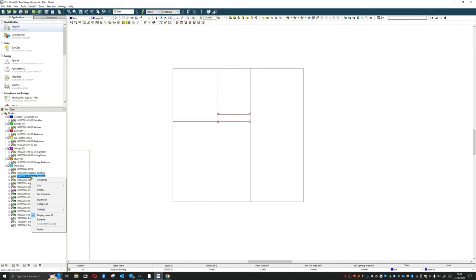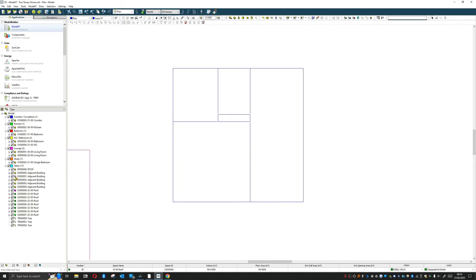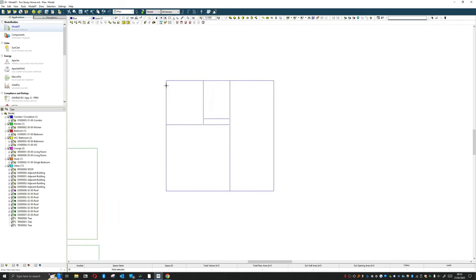I would avoid putting in staircases, because if they're on an external wall they can sometimes require frost protection - we might set a setpoint of 14 or 16 degrees within those spaces. For very tall buildings we might also care about heat gains on the topmost floor. But to set a space as a void, go to Properties, and under object subtype, hit Void - you'll see that the yellow tile is now greyed out. That's all a void is.